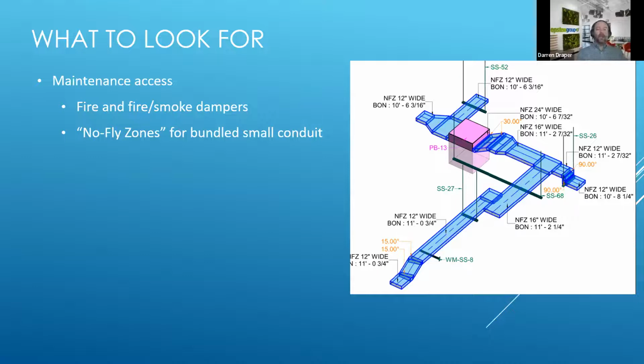Another really big one for us is fire smoke dampers, ensuring those can be gotten to. In a BIM model, you can check that access panels have actually been included. That should be modeled down to the floor for a fire damper, to ensure you can get up to the access panel to even inspect or re-engage the damper. Fire smoke damper actuators also have to be accessible, modeling clearance out and down for that as well. Not everything is going to be easy to maintain, but the BIM process helps figure out where you'll have struggles or where things could be improved.